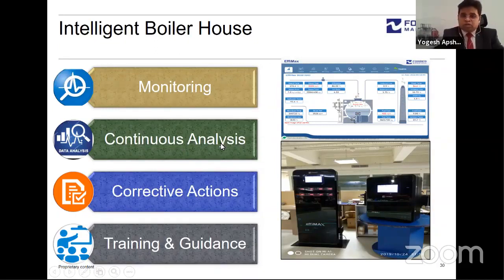Then what we do is the continuous analysis. So we measure the pulse of the boiler. So what is the pulse of the boiler? What is the direct efficiency of the boiler? What is the indirect efficiency of the boiler? What is the steam to fuel ratio of the boiler? What is the cost of steam? All this continuous analysis we are giving back to the operators and the management.